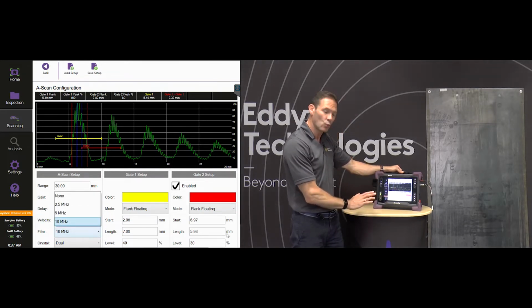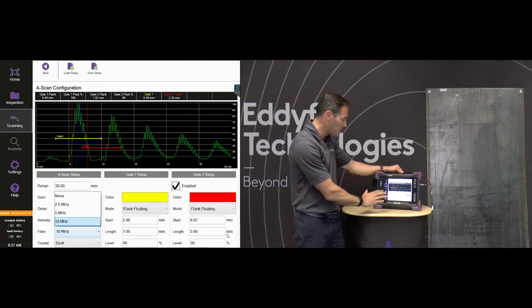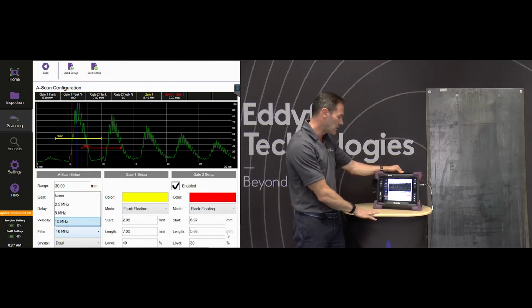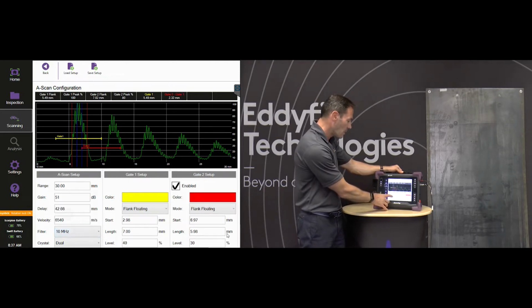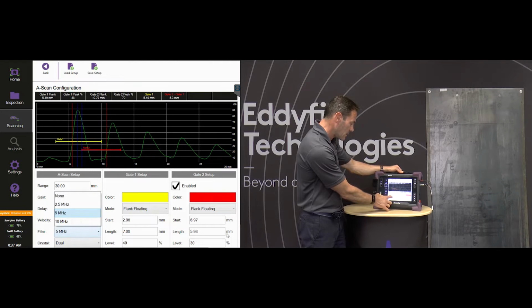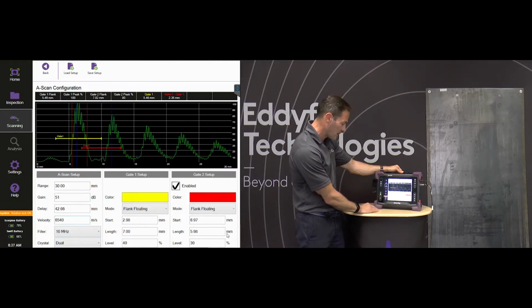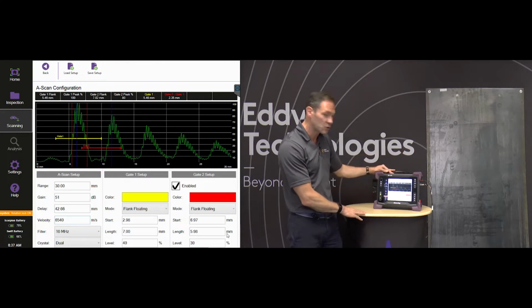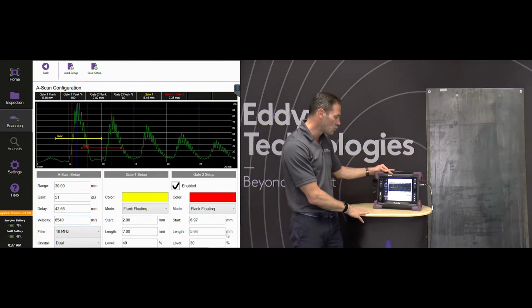In this case I don't want any filtering. It's a 5 megahertz probe, so if I put it at a 10 megahertz filter it basically won't filter anything, but I can also smoothen the A-scans if I'd like to. The crystal option in this case is dual, because it's a dual element probe, so we're going to leave that at dual, but the system can also handle a single element probe.